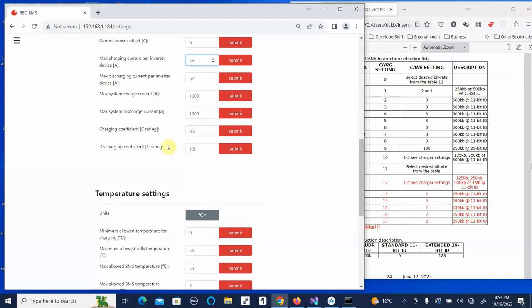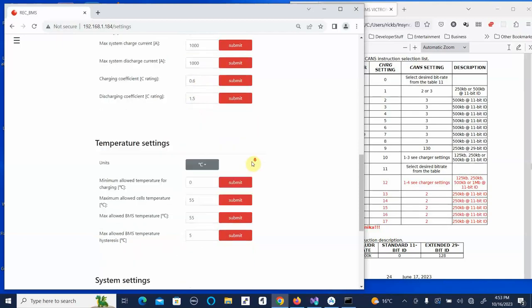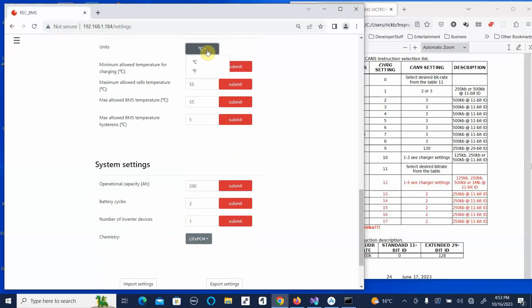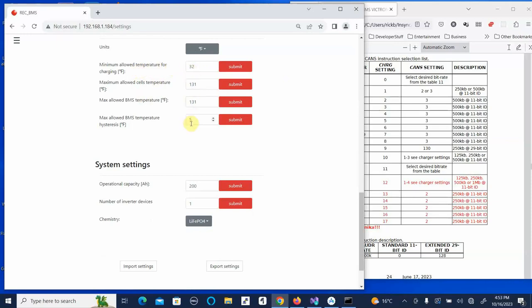These are your standard charging and discharge coefficients. We pick our engineering units here, Fahrenheit or Celsius. And then we can set a minimum and maximum temperature. The maximum allowed BMS temperature will disable your top balancing if it gets above this point. There are internal resistors within the BMS, and your BMS will start to get warm, trying to bleed off the excess capacity if the cells are not balanced for any reason.